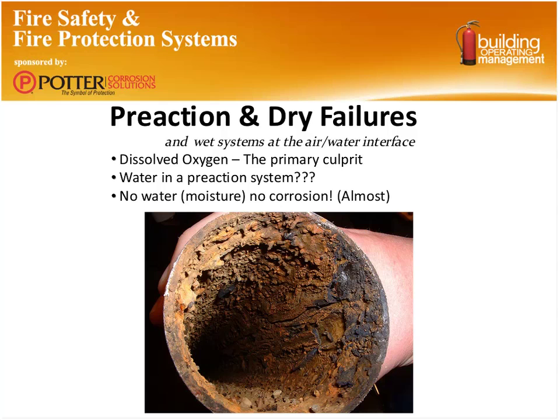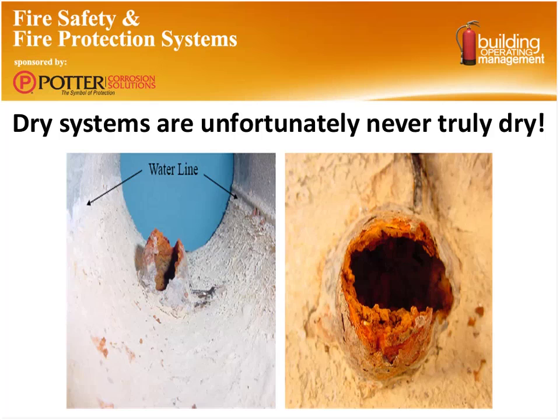There is water inside the system from maybe some initial testing. Maybe you had a false actuation and put water in the pipe. If you didn't go and pull all the sprinkler heads out, there's probably a little bit of water down in the bottom of that piping. So unfortunately, most systems are never truly dry.